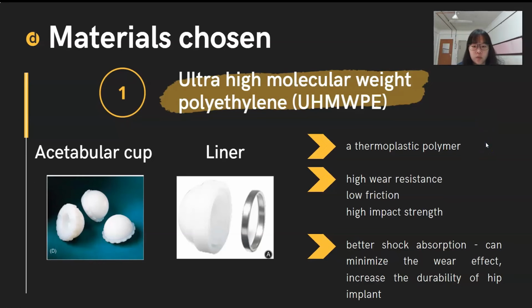The material chosen to make the acetabular cup and the liner is ultra-high molecular weight polyethylene. This polyethylene is a thermoplastic polymer due to its extremely long chain with limited or no cross-link. It has high wear resistance, low friction, and high impact strength. Therefore, it has better shock absorption that can minimize the wear effect at the hip joint and increase the durability of the hip implant.